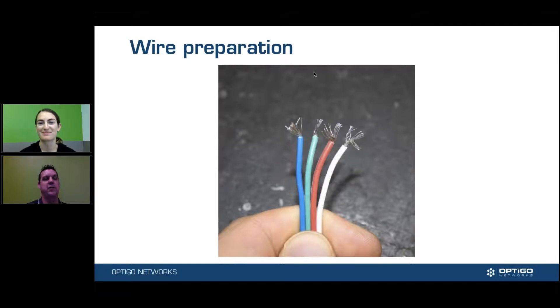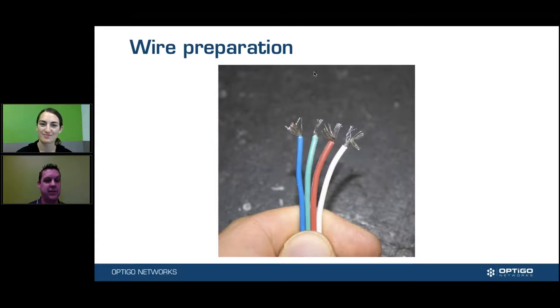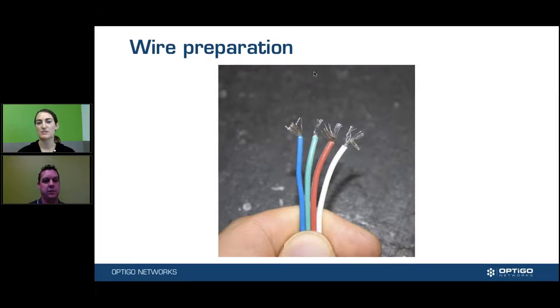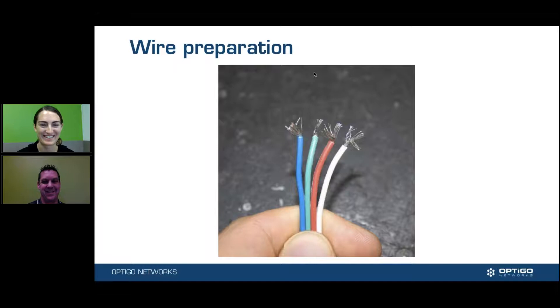Wire preparation is absolutely key. You want it nice and twisted, make sure you don't have any loose strands, and make sure your insulation is stripped back far enough so you can actually put it under the terminal and it makes connection. All of these things don't seem as critical as they are, but any one of these that you've missed will mess up your MSTP network. So just to be clear, we don't want it to look like this picture — no, this probably isn't going to get you too far.